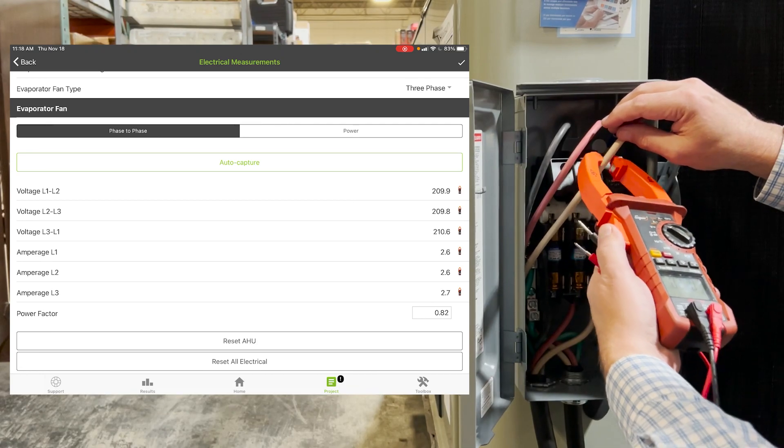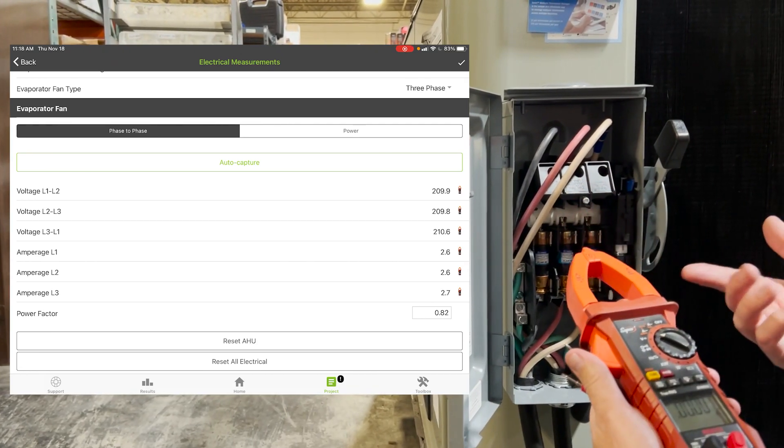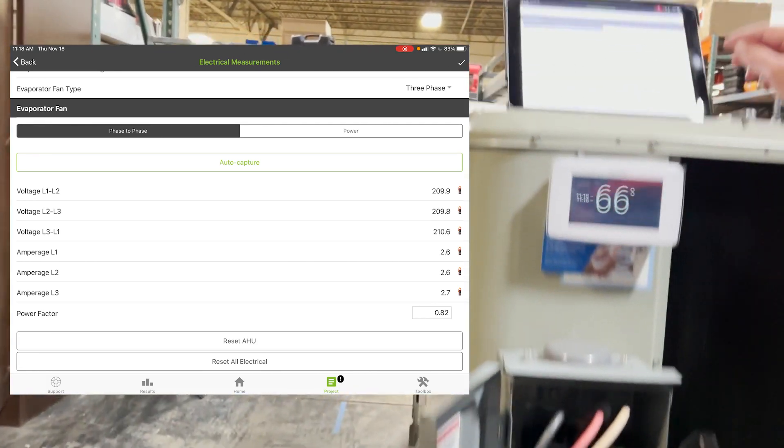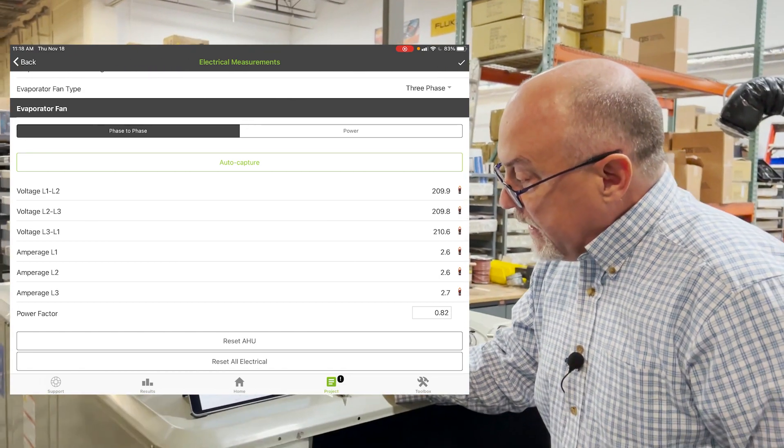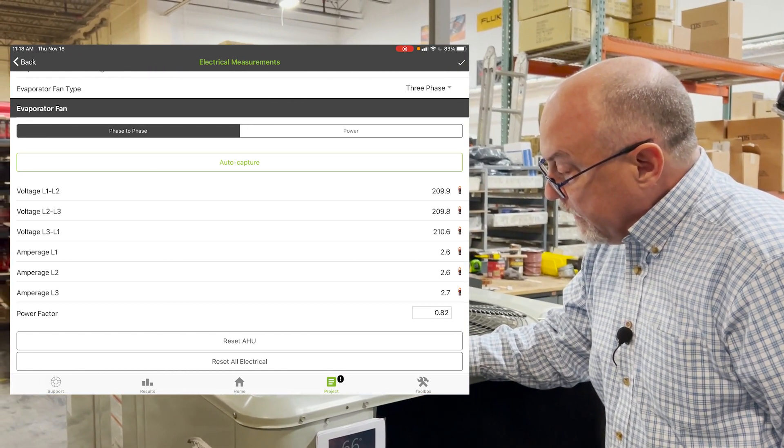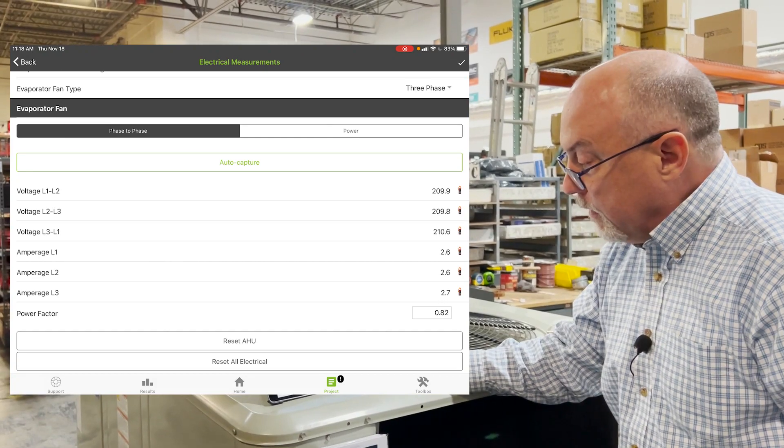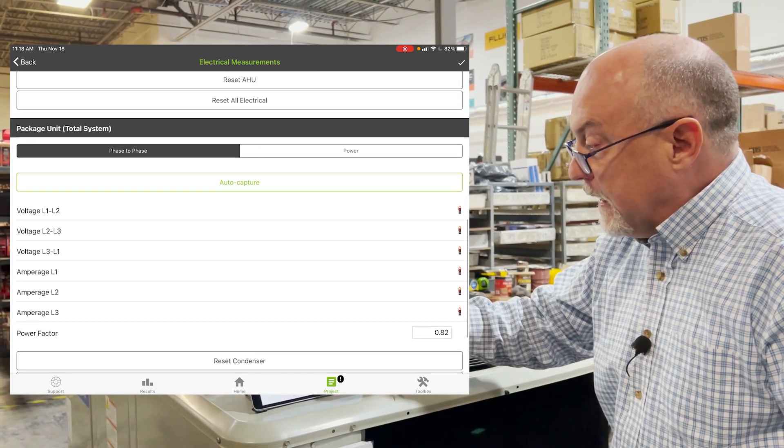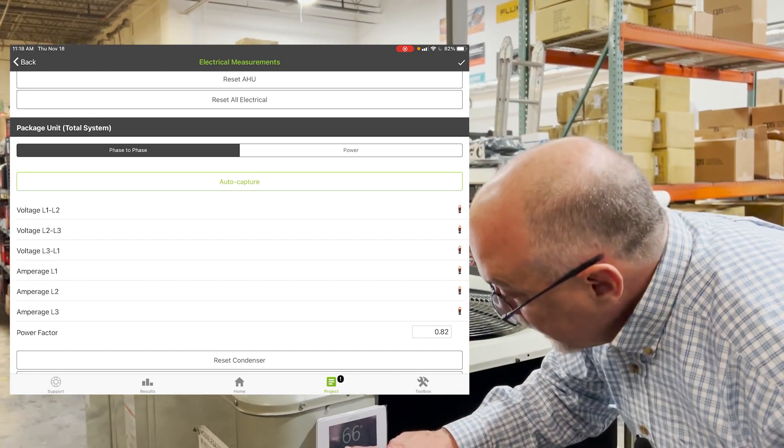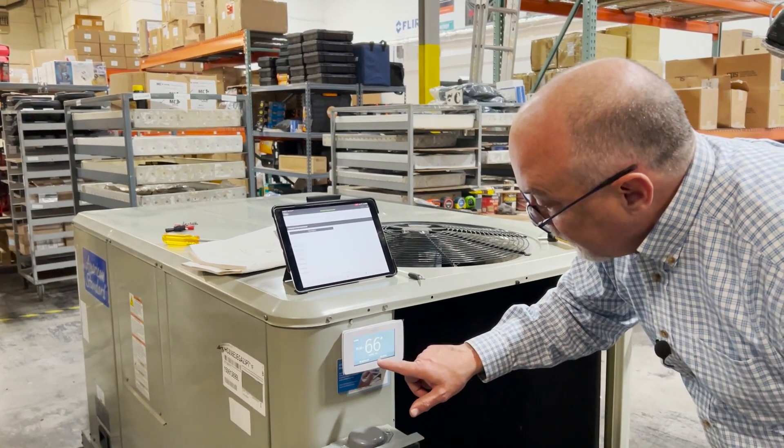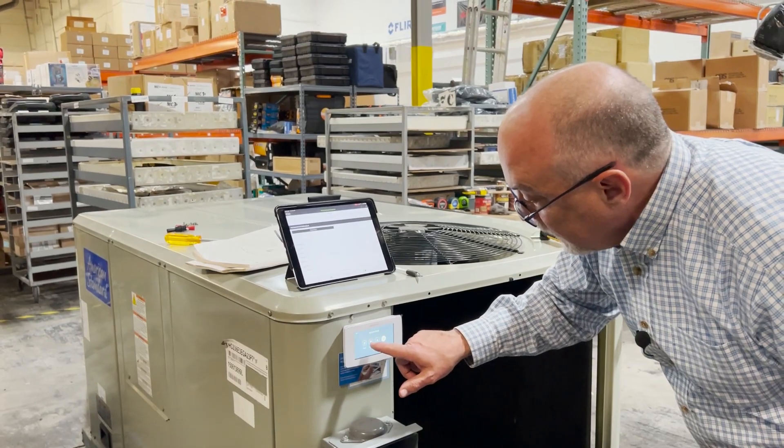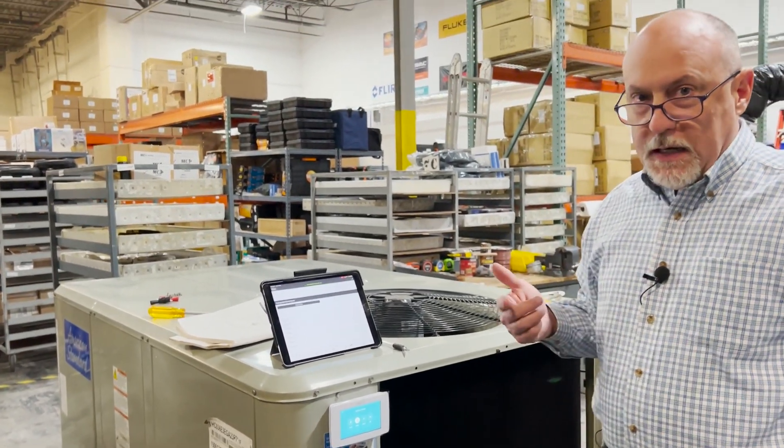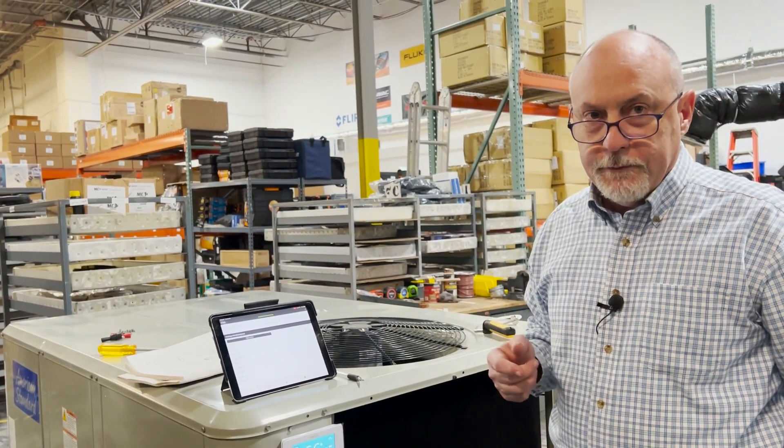So this allows us to do all the voltage readings real quick without having to hit the capture button. And if we come up here now, we can check these. So as you can see, I'm 209, 209, 210, 2.6, 2.6, 2.7 on phase three. So now I can scroll down here, and I want to move down and capture them at the condenser. So now what I'm going to do is turn the system to on, and we'll give this a few minutes to stabilize, and then I'll come back.